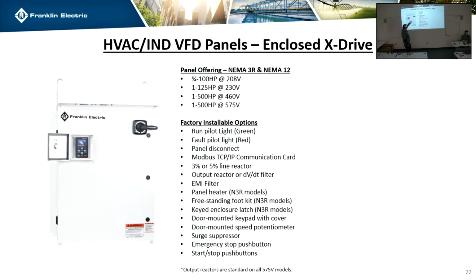Yep. So basically we have green run lights, red fault lights, panel disconnect, the communication card like I talked about. This is for Modbus only. 3 and 5% line reactors. The bigger drives for X drive have a DC choke that's equivalent to 3%. So you don't need a line reactor, but if you need 5%, we put a 3% line reactor in there and the drive becomes 5% equivalent.